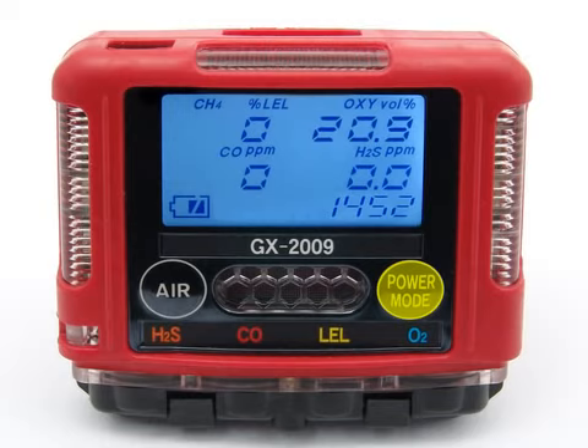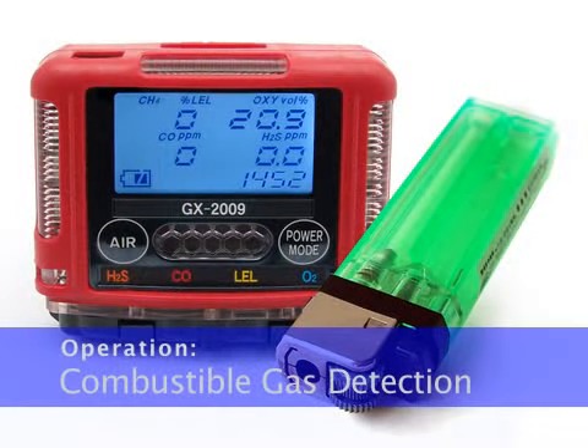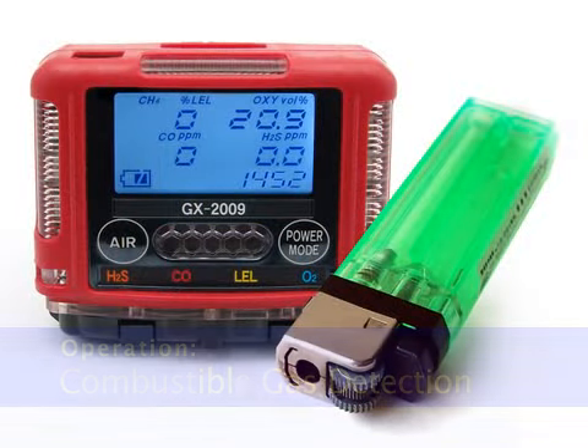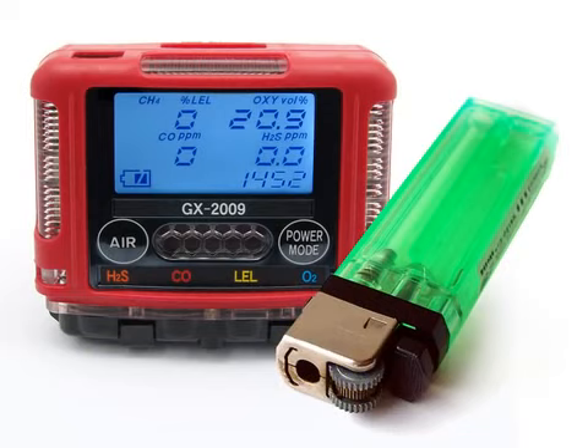If you do not press the button for 20 seconds while in display mode, the GX2009 will return to measuring mode automatically, and the backlight will turn off 30 seconds after the last button was pressed. Do not expose the combustible sensor to high concentrations of combustible gas, such as that from a butane lighter. Exposure to high concentrations of combustible gas may adversely affect the performance of the sensor.